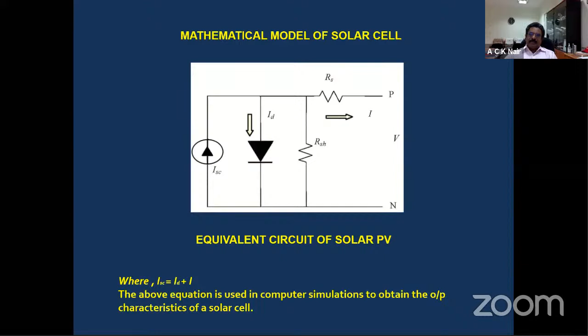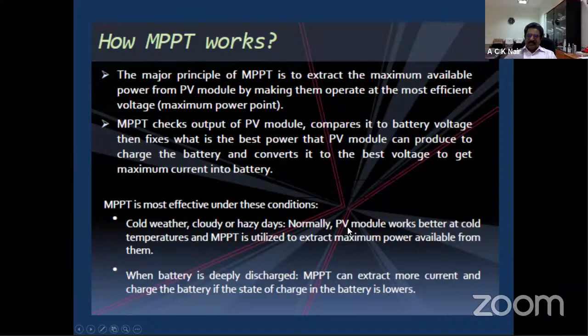The main principle of MPPT is to extract the maximum available power from PV modules by making them operate at the most efficient voltage, the maximum power point. MPPT checks the output of the PV module, compares it to the battery voltage, and fixes the best power that the PV modules can produce to charge the battery, converting it into the best voltage to get maximum current into the battery. MPPT is most effective under conditions like cold weather, cloudy days, or when the battery is deeply discharged.